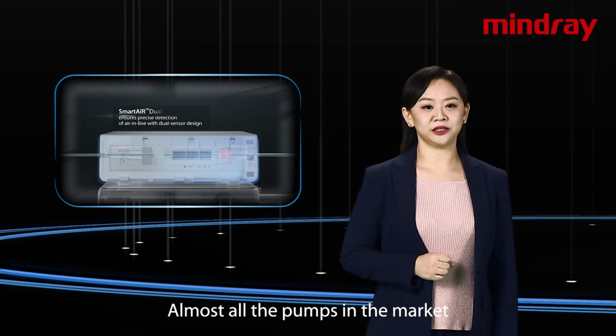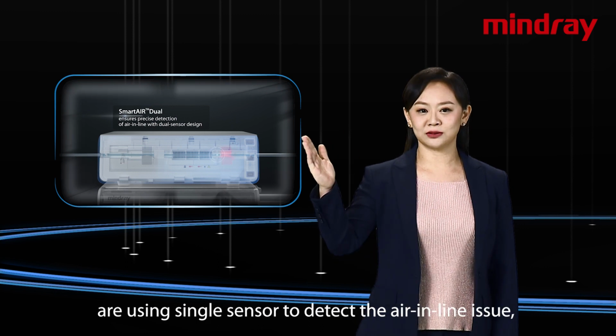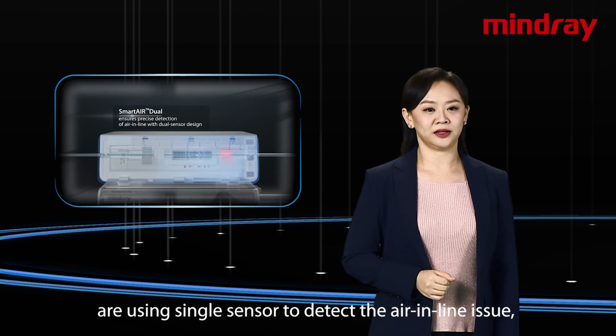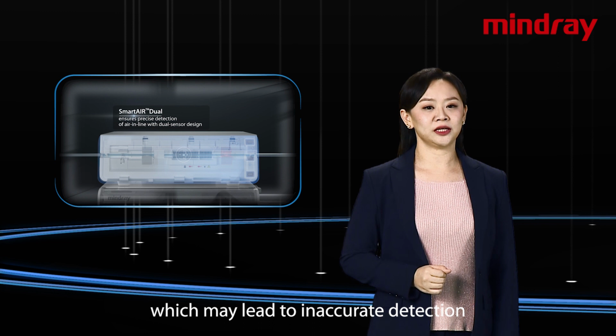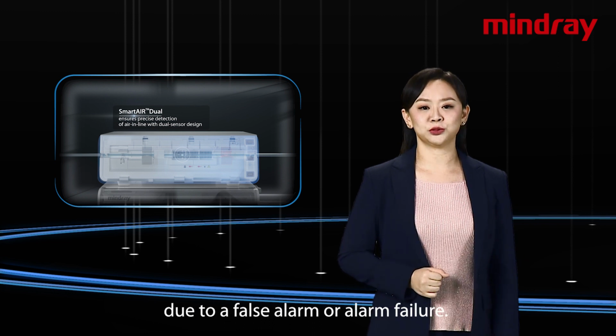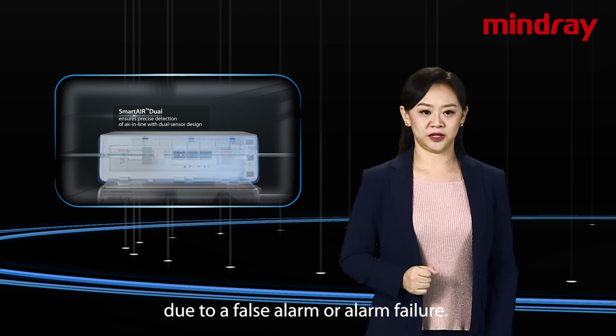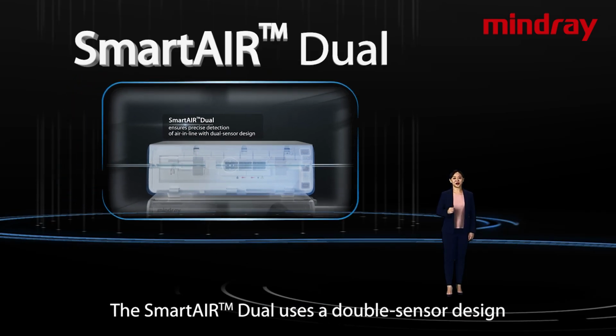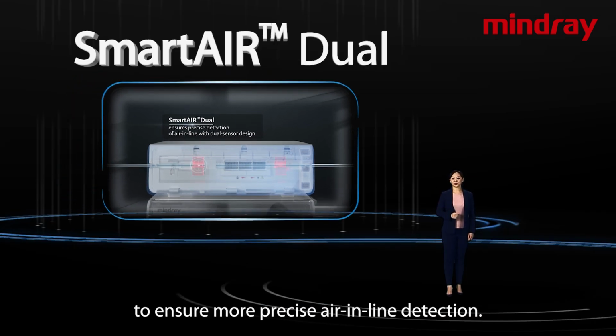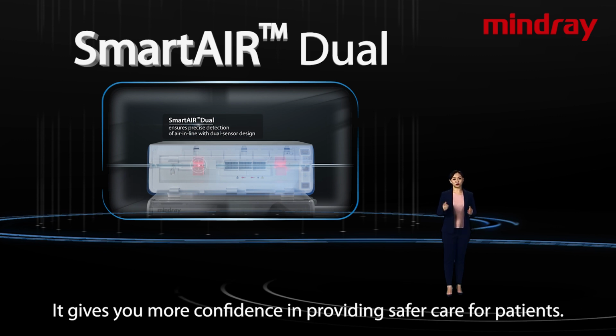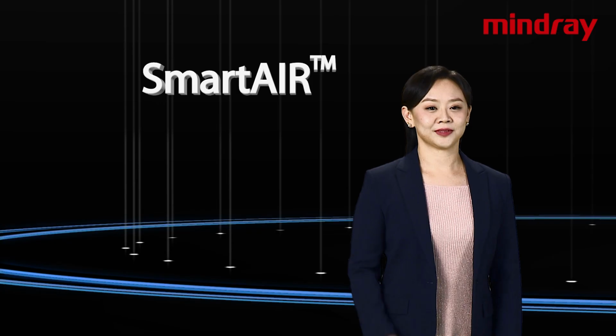Almost all the pumps in the market are using single sensor to detect the air in line issue, which may lead to inaccurate detection due to a false alarm or alarm failure. The SmartAIR Dual uses a double sensor design to ensure more precise air in line detection. It gives you more confidence in providing safer care for patients.